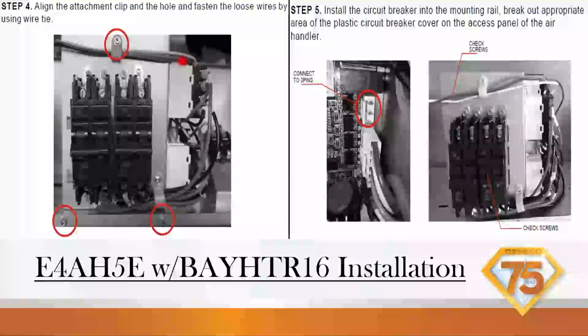If you do find, and this goes for all equipment, a wire that's rubbing on the metal and it's pulled so tight and it's still rubbing, I always carried a small tube of caulking in my bag. I would put a bead of caulking in between that wire and the metal part, and it creates a little insulating field in there and it won't rub through. So keep that in mind. That's something I always did on maintenances too. If you saw a bunch of little bead caulks on the wires, I was probably in there.